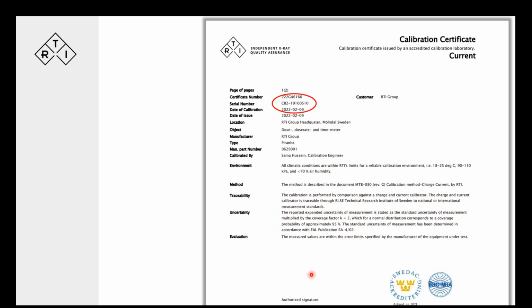So you get all this, and then you get the calibration data. But the important thing here is the calibration traceability of it. So here, in effect, we can trace the validity of individual samples of a measurement to a calibration certificate to make that point if necessary. It's an extreme, but that's a possibility. All right, so that's kind of interesting, how much further we can move the limits of traceability from where they are in general today.